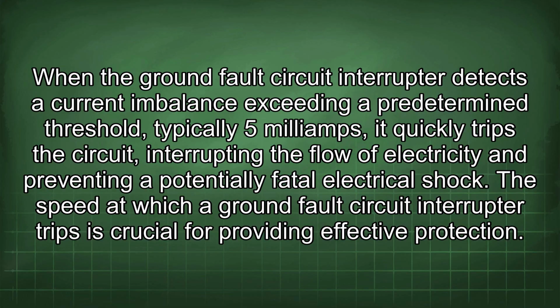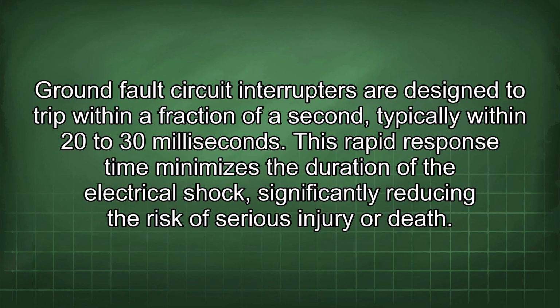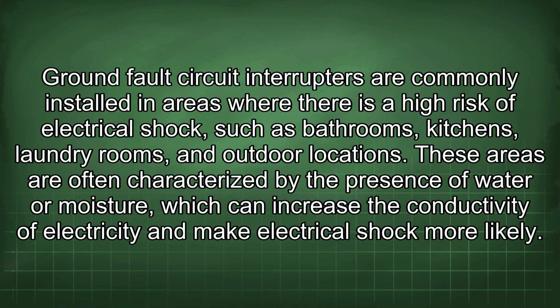The speed at which a ground fault circuit interrupter trips is crucial for providing effective protection. Ground fault circuit interrupters are designed to trip within a fraction of a second, typically within 20 to 30 milliseconds. This rapid response time minimizes the duration of the electrical shock, significantly reducing the risk of serious injury or death. Ground fault circuit interrupters are commonly installed in areas where there is a high risk of electrical shock, such as bathrooms, kitchens, laundry rooms, and outdoor locations. These areas are often characterized by the presence of water or moisture, which can increase the conductivity of electricity and make electrical shock more likely.